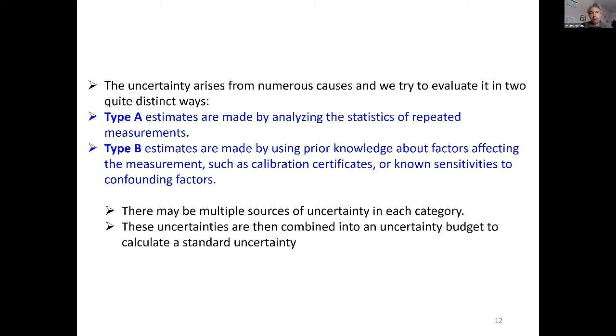Type B, the guide says, is everything else. It makes it very easy. So type A is statistics with a distribution. Type B is everything else you have. But this everything else arises from technical knowledge. You may have calibration, resolution, all the wordings we had yesterday, stability, drift, correct use, exposure, influence quantities in the field, other relationships between quantities, voltage generator over an ohm measurement, and so on. All of them are then combined into what we call an uncertainty budget to calculate the standard uncertainty.